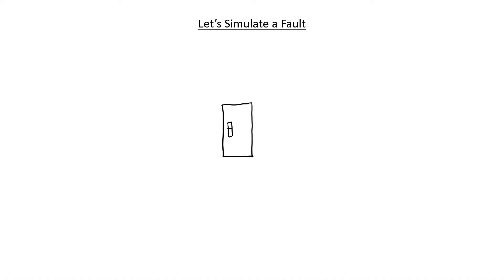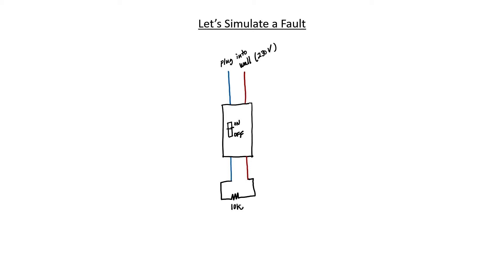In a minute, we're going to go over to the bench and simulate one of these fault conditions. Let me draw out first what I intend to do and then we'll go and test it. We'll be plugging our circuit breaker into the wall and giving it 230 volts. I'll be attaching a 10 kilo ohm load resistor to our circuit breaker. That should draw about 23 milliamps from the wall. We need to make sure that our resistor can handle that much current draw, so anything more than about 5 watts should be fine.